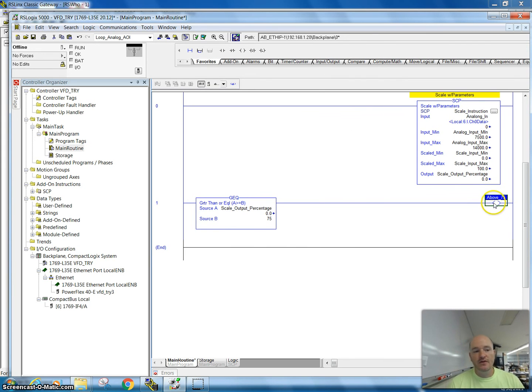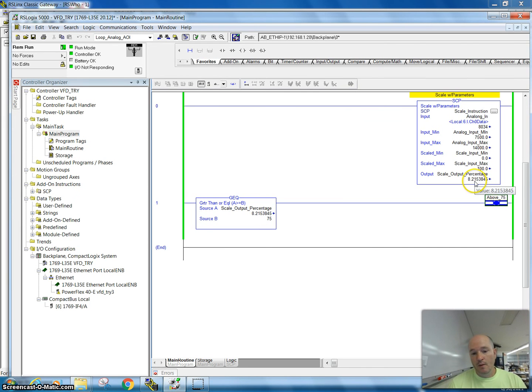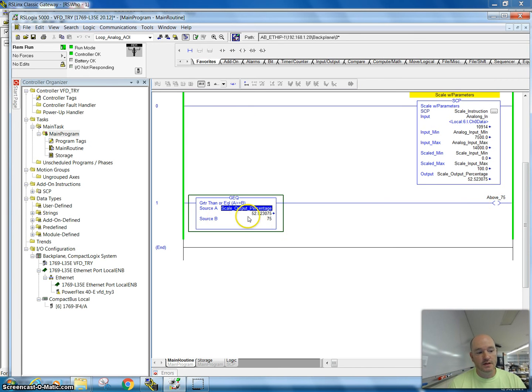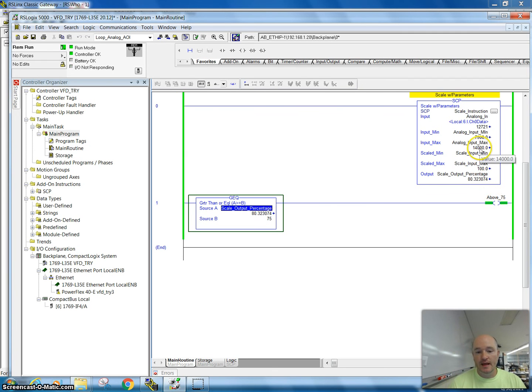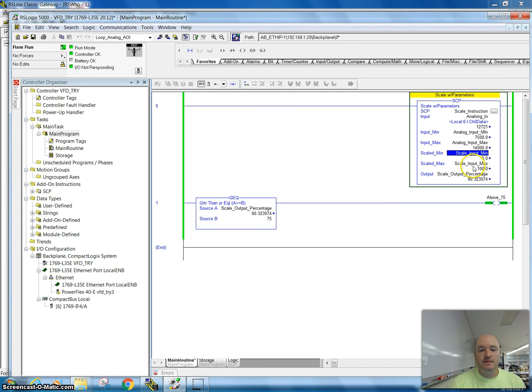When we're above 75, this bit would go true. Notice we don't have any inputs in front of this rung — sometimes you will, most of the time you won't. So I'll go ahead and download this. We're at about 1% and we're going to start cranking it up. Once we get to 75 you'll see this bit go true, because the greater-than-or-equal-to is at and above 75. Now we're above that 75% threshold. I could even come in here and override by typing a value like 12,000, and look how that changes the percentage. This offers a lot of flexibility when you use tags instead of just inputting numbers.